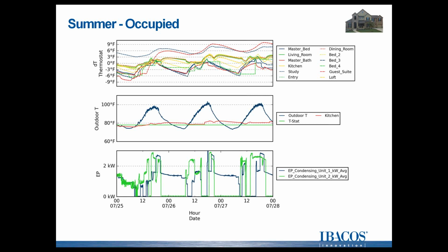Some conclusions we can draw here are that large open spaces can be effectively conditioned from these simplified systems, but it's crucial that you have the correct placement and correct register selection for that single point of distribution. Is it ready for every house out there? Certainly not, and that's something we've found through this testing, and we found some potential ways to help improve those cases when it did not work correctly.